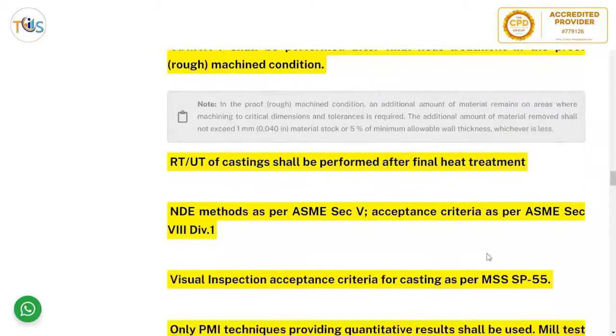In the proof-machine condition, an additional amount of material remains on areas where machining to critical dimensions and tolerances is required. The additional amount of material removed shall not exceed 1 mm (0.04 inch) of material stock or 5 percent of minimum allowable wall thickness, whichever is less. RT and UT of castings shall be performed after final heat treatment, because cracks might grow during heat treatment intended for stress relaxation.